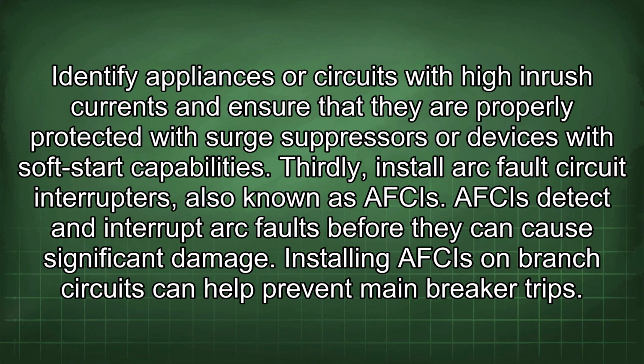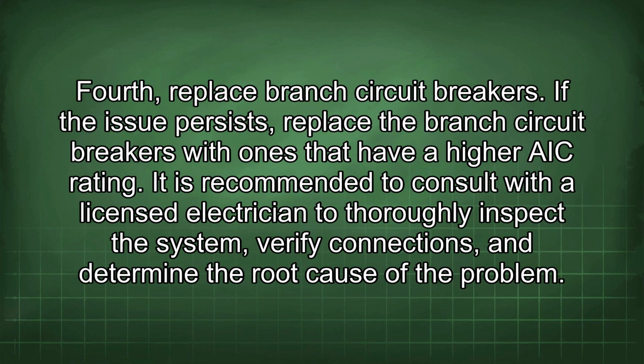with soft start capabilities. Thirdly, install arc fault circuit interrupters, also known as AFCIs. AFCIs detect and interrupt arc faults before they can cause significant damage. Installing AFCIs on branch circuits can help prevent main breaker trips. Fourth, replace branch circuit breakers. If the issue persists, replace the branch circuit breakers with ones that have a higher AIC rating.